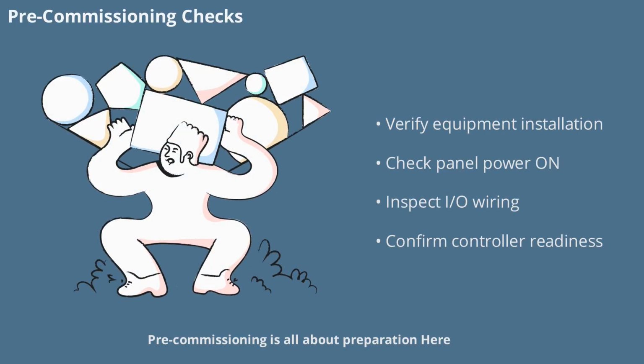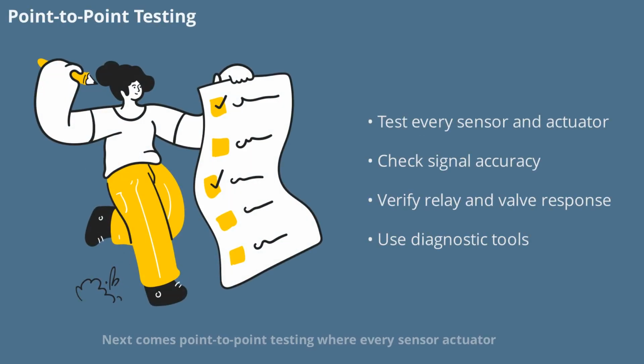Pre-commissioning is all about preparation. Here we verify that all equipment is installed correctly and panels are powered on. I/O wiring is checked for continuity and correctness, and controllers are confirmed to be ready for operation. This stage lays the groundwork for everything that follows, ensuring that the system's foundation is solid before moving on to more detailed testing.